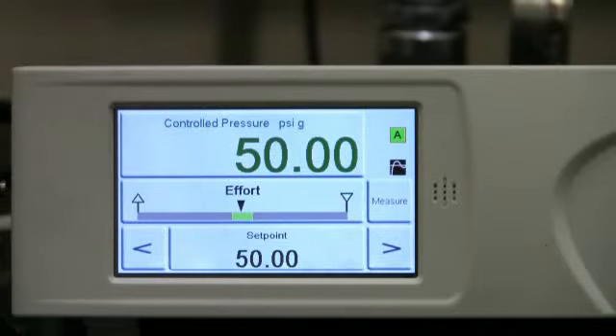Notice how fast the PACE5000 controlled to 50 psi. Once the set point is achieved within user-defined limits, the color of the pressure display will change from blue to green, providing immediate feedback to the operator that the reading from the device under test can now be recorded. Since the effort meter is in the green zone, we have a leak-free setup and can proceed with the calibration run.